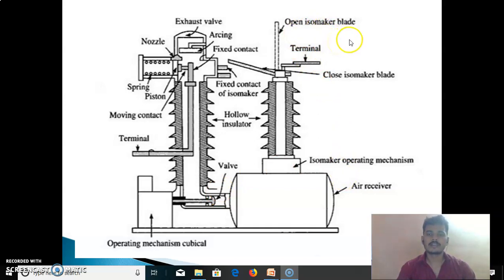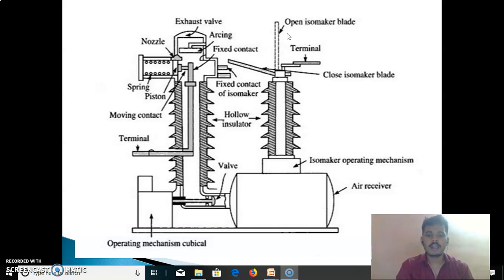The advantages of the air blast circuit breaker include: cheapness and free availability of the interrupting medium, chemical stability and inertness of air, high speed operation, fire hazard is eliminated unlike in oil circuit breakers, and short and consistent arcing time resulting in less burning of contacts.